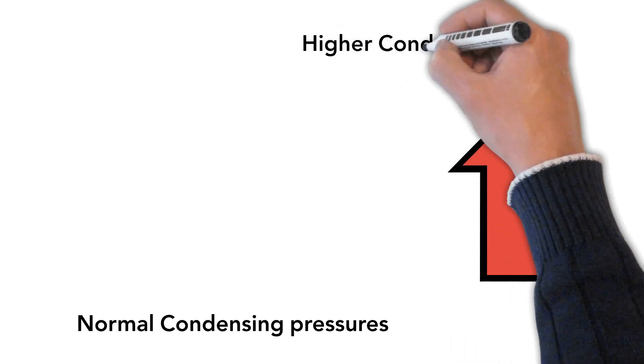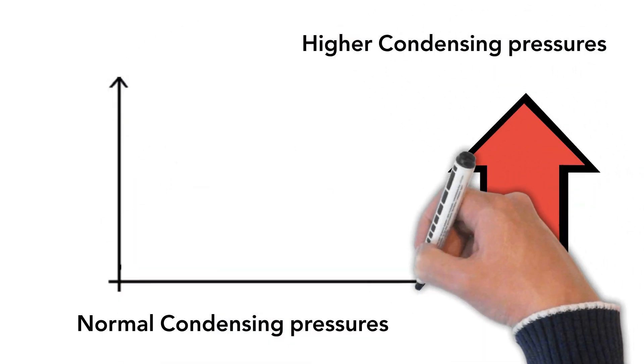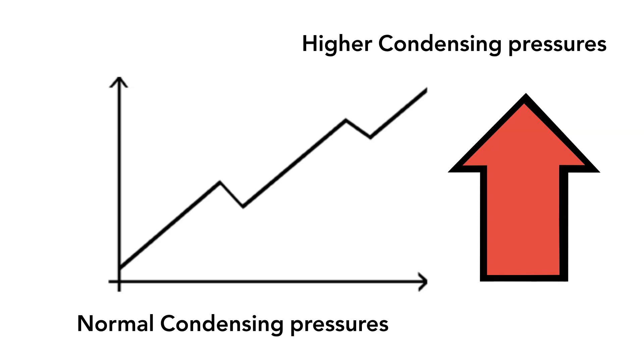If non-condensable materials, such as air, are not removed, the system will operate at higher than normal condensing pressures.